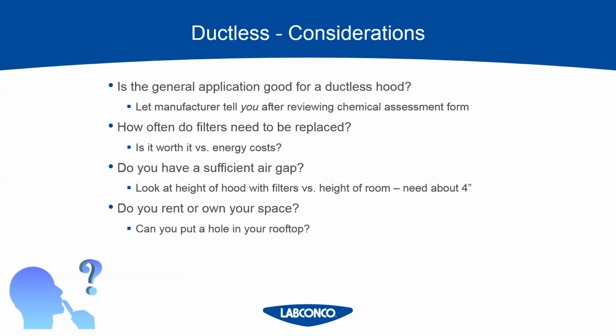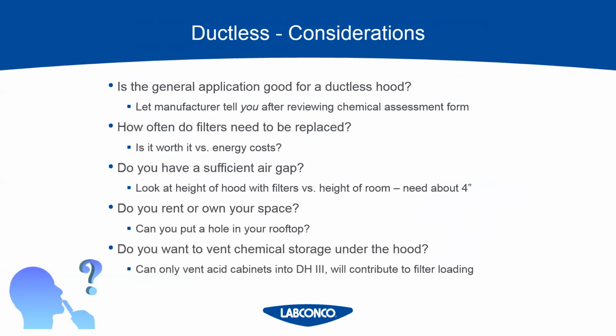But that's something to consider. Can you put holes in your walls and rooftop? Do you want to vent chemical storage under the hood? This is something that gets overlooked when people assume that they can vent things into the hood. The only option for venting with ductless hoods is your acid cabinet into a DH3. So you can't do it into a DH2 or DH1. And you have to think it contributes to the filter loading.